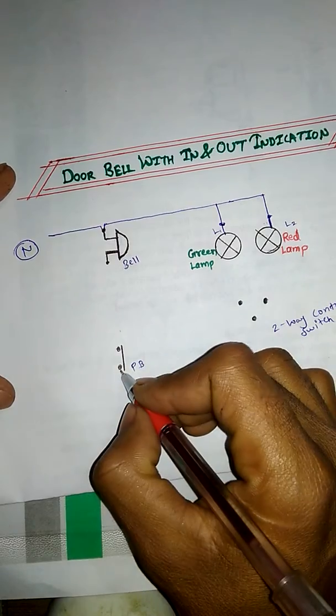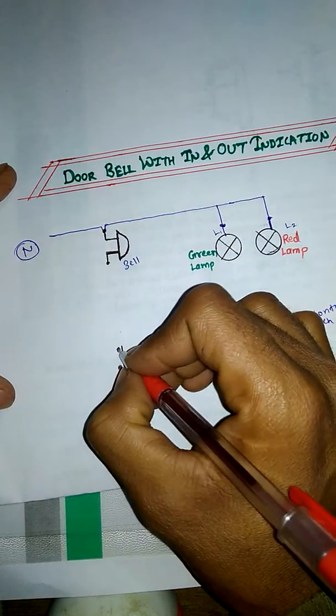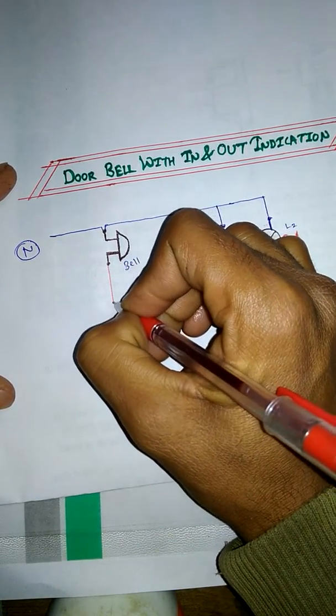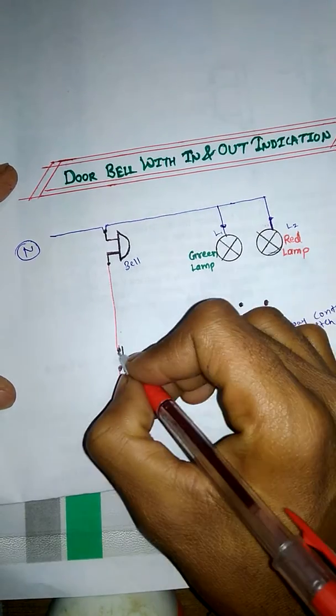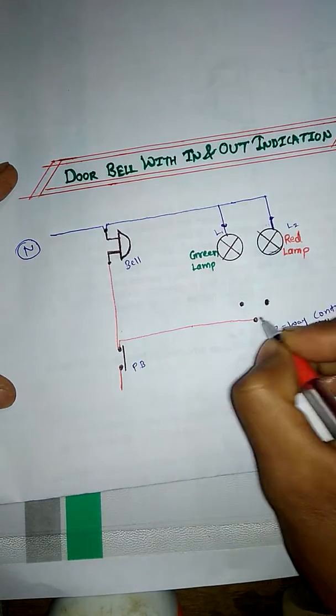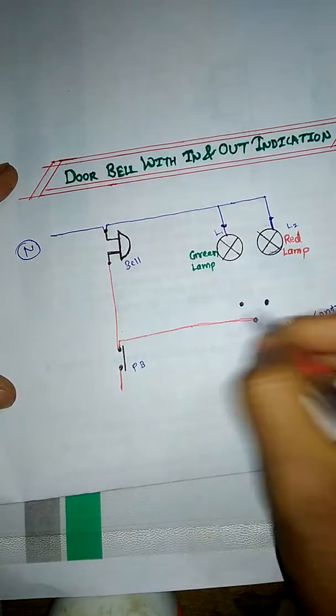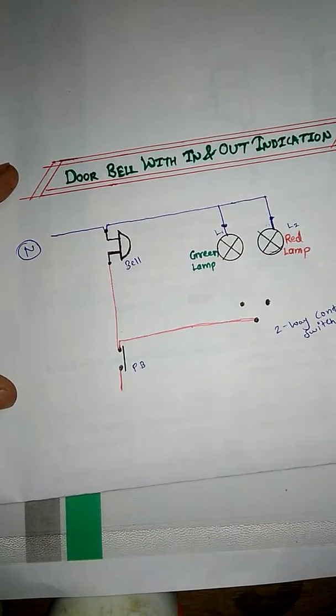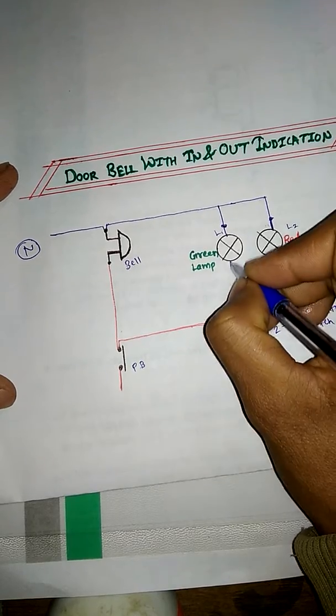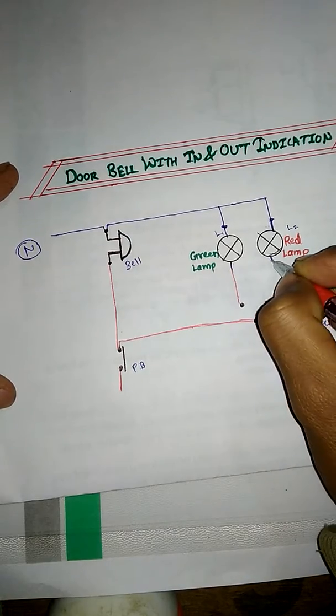Now for phase. Give phase to the push button and connect the output terminal with the buzzer, and loop it with the incoming terminal of the two-way control switch. Give the two terminals of the two-way switch to red and green lamp respectively.